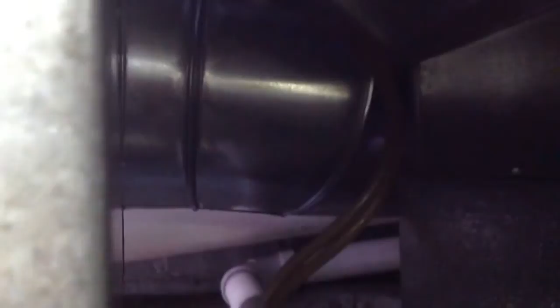So I just want to show you that you can use round ductwork on your return air if you need to add more airflow. It's okay to do that. In fact, your round flows a little better than your square. So even 10-inch will get the job done, as will many 8s. If your 8-inch flows 200 and you add 5 of them, it's probably like 1,000 cfms, which is quite considerable. So keep this in mind when you're short on return air.